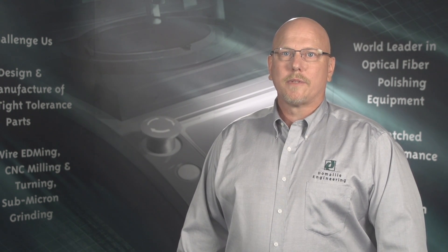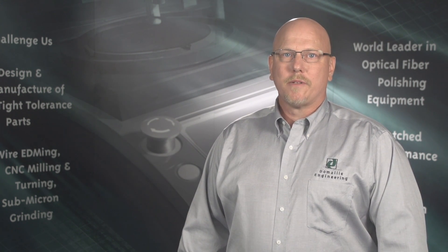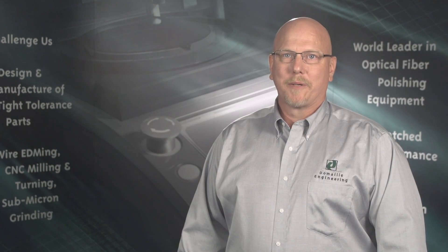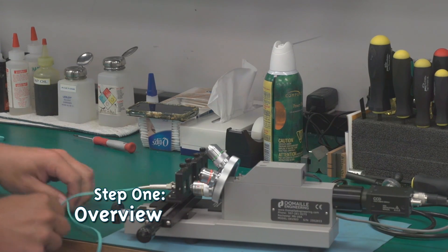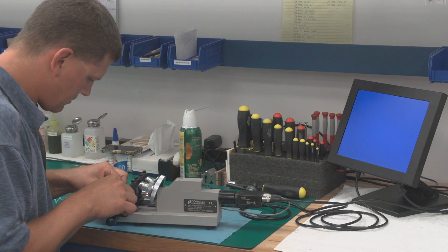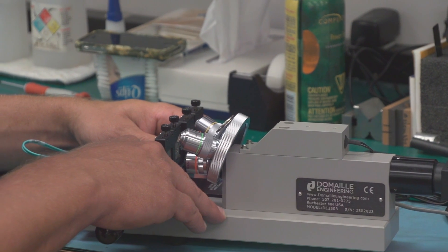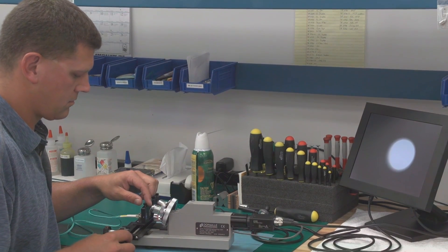The following video will take you step-by-step through the simple process of unpacking, setup, and operation of your DE2503 video microscope. Thank you for choosing Domaille Products. Step 1: Overview. The DE2503 video microscope is designed for visual end-face inspection of fiber optic connectors in a production environment. The DE2503, our most popular model, is equipped with a four-position linear slide that can be loaded with four different connector adapters.